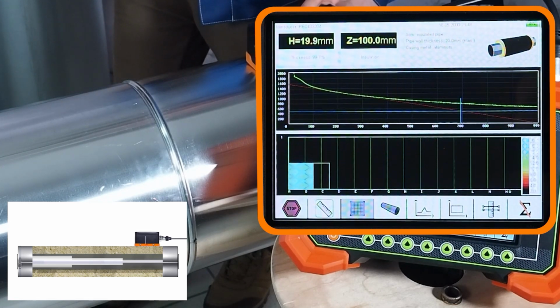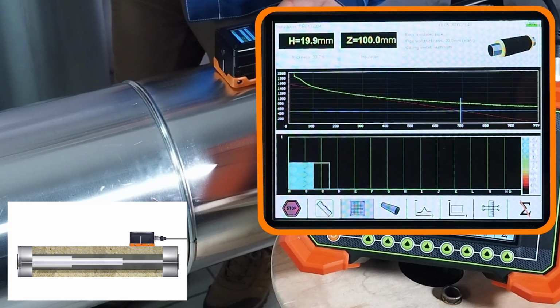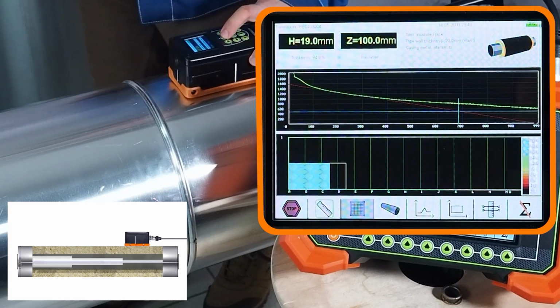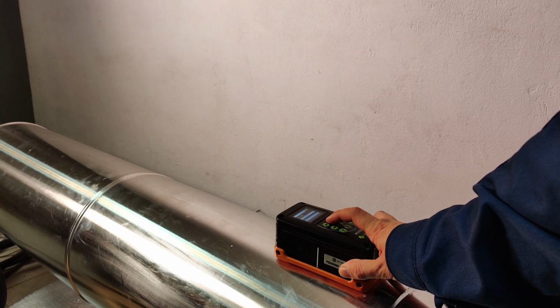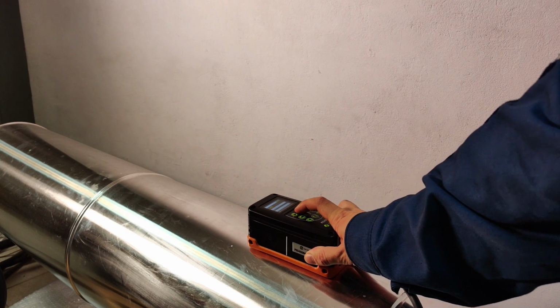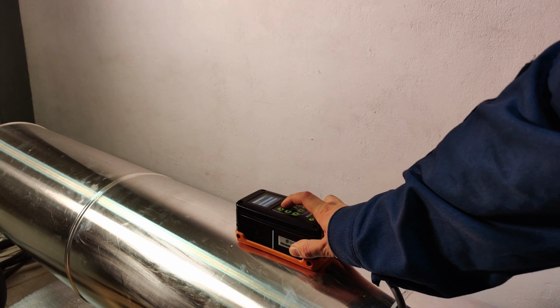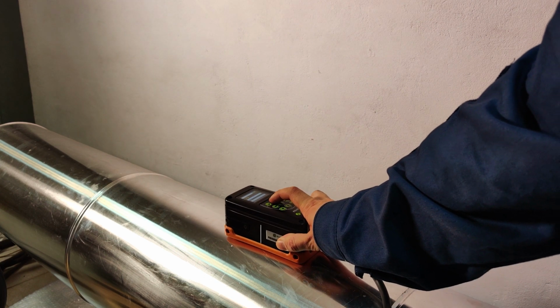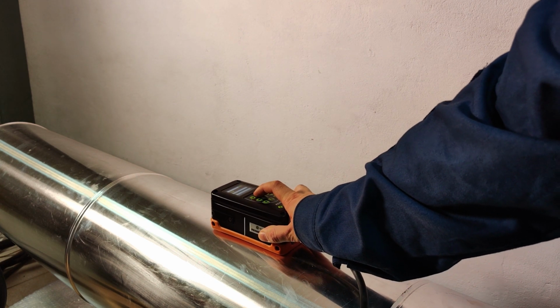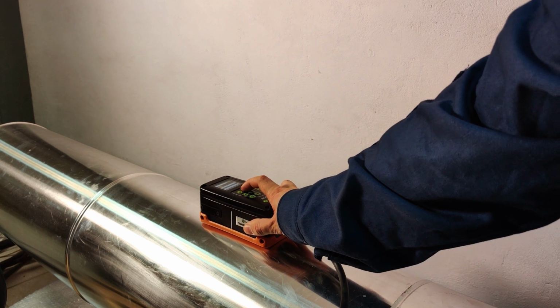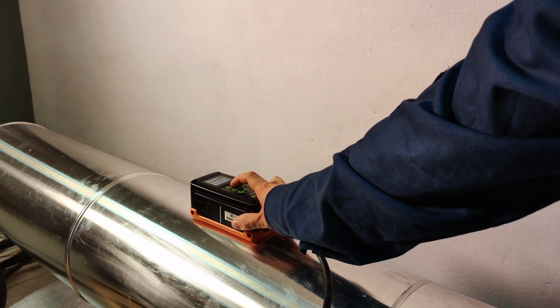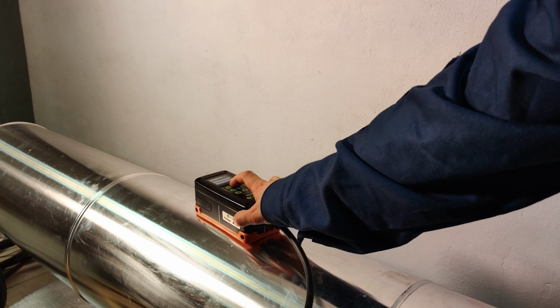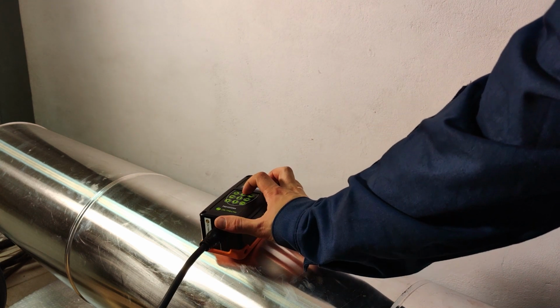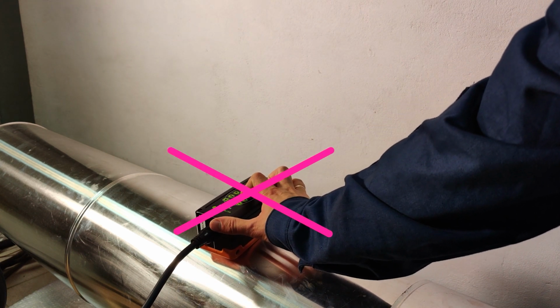If we see a wall thickness in any item area greater than we got during the calibration, then it is possible we calibrated in an area with a defect, so we should recalibrate after selecting a point for calibration in another area. As you see, we do not rotate the sensor when measuring the item. The magnetic field has a complex spatial geometry, so, with significant rotations of the sensor relative to the item, we can lose the accuracy of measurements.